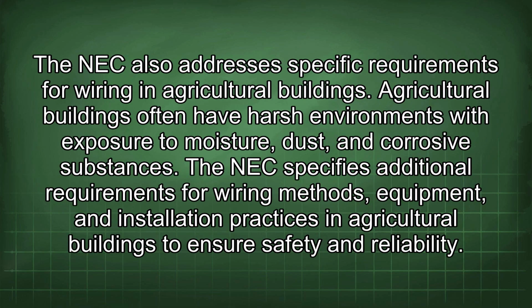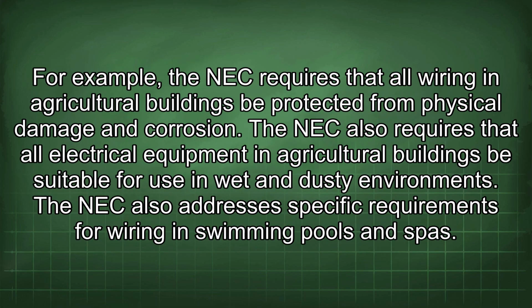The NEC also addresses specific requirements for wiring in agricultural buildings. Agricultural buildings often have harsh environments with exposure to moisture, dust, and corrosive substances. The NEC specifies additional requirements for wiring methods, equipment, and installation practices in agricultural buildings to ensure safety and reliability. For example, the NEC requires that all wiring in agricultural buildings be protected from physical damage and corrosion. The NEC also requires that all electrical equipment in agricultural buildings be suitable for use in wet and dusty environments.